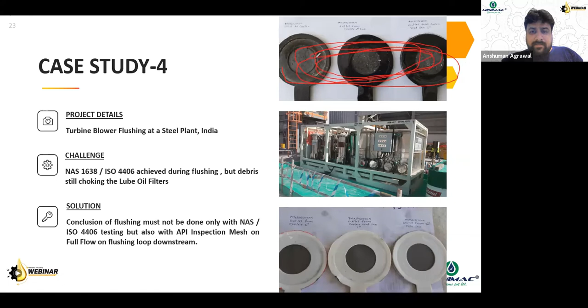When you perform a mesh inspection, you ensure the entire loop of the pipeline has been cleaned of debris, and only then should you apply the NAS standards. Interestingly, the NAS standard reading remained the same throughout the flushing, but the mesh inspection screen got progressively cleaner as we concluded the flushing activity at this site.